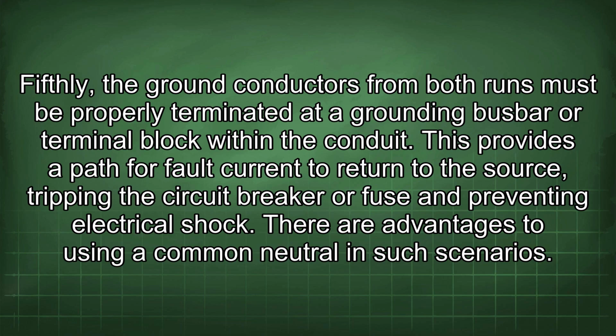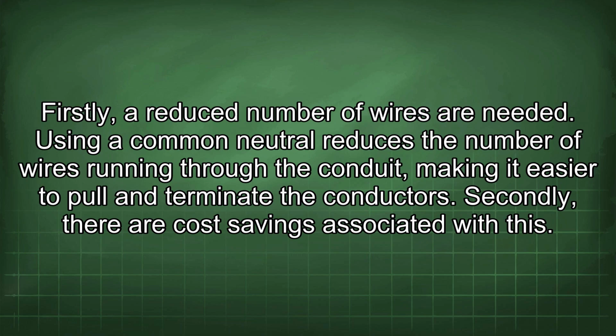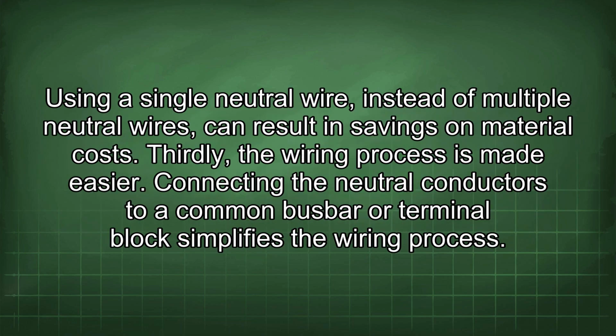There are advantages to using a common neutral in such scenarios. Firstly, a reduced number of wires are needed. Using a common neutral reduces the number of wires running through the conduit, making it easier to pull and terminate the conductors. Secondly, there are cost savings associated with this. Using a single neutral wire instead of multiple neutral wires can result in savings on material costs. Thirdly, the wiring process is made easier. Connecting the neutral conductors to a common busbar or terminal block simplifies the wiring process.